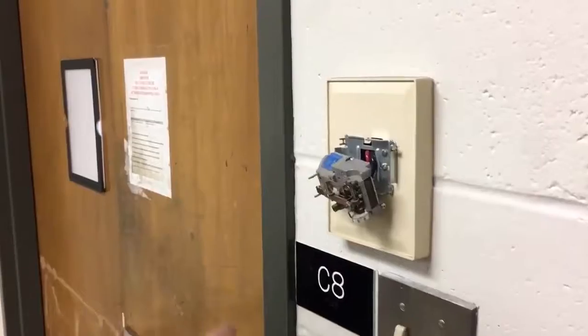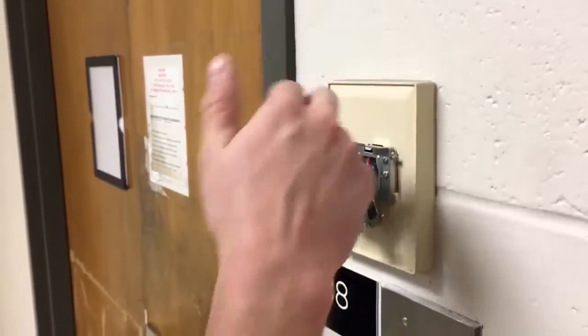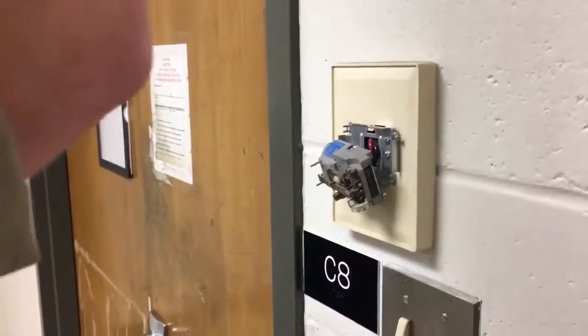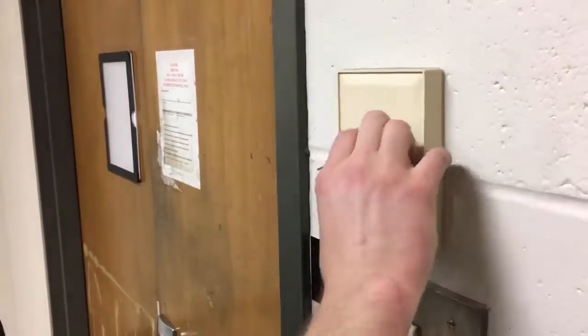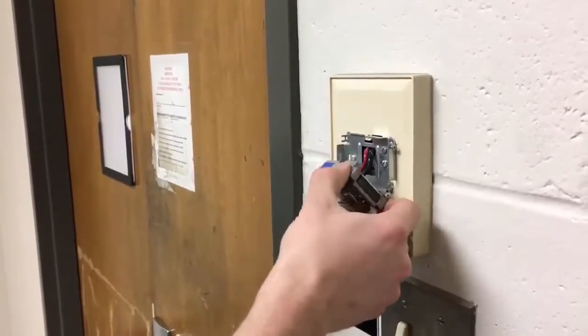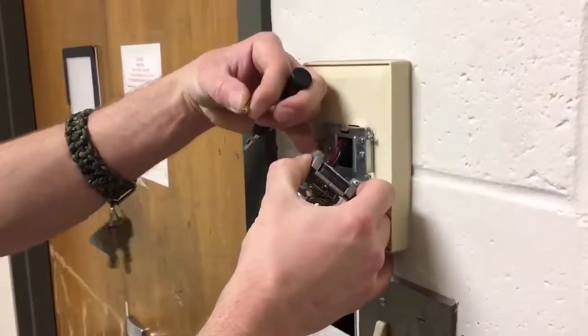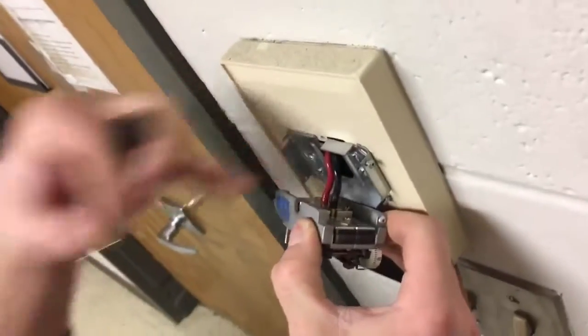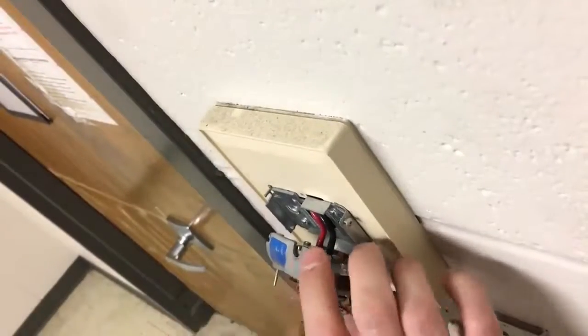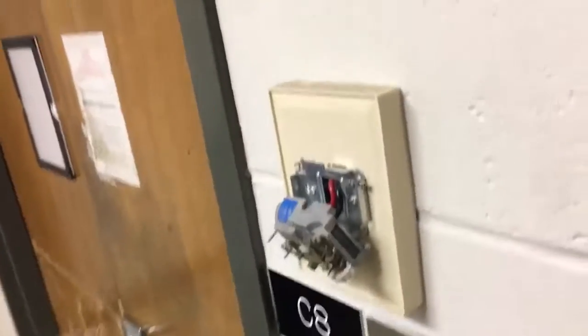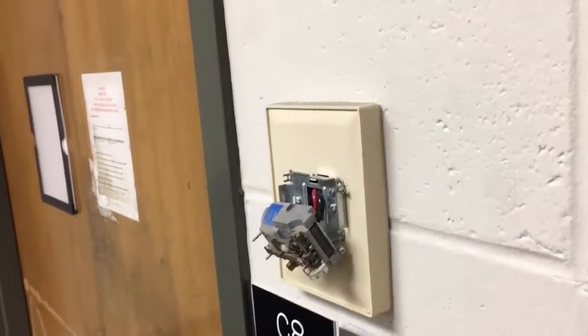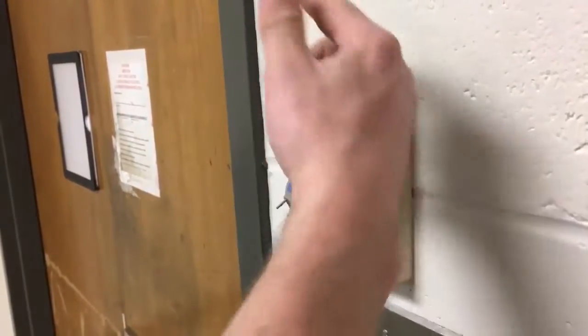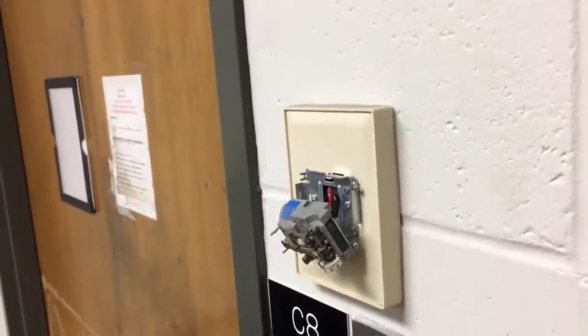Usually an easy way to tell whether it's at the stat itself or if it's up at a valve or damper or somewhere in the wall: if you take the cover off, you can check the seal on the back. If you hear the leak right here, then the thermostat seals are bad and they'll need to be replaced. If it were a quieter environment, you could check to see if this has a metallic sound to it, like it's ringing. That indicates air is just blowing through the thermostat and not a leak at the stat itself.